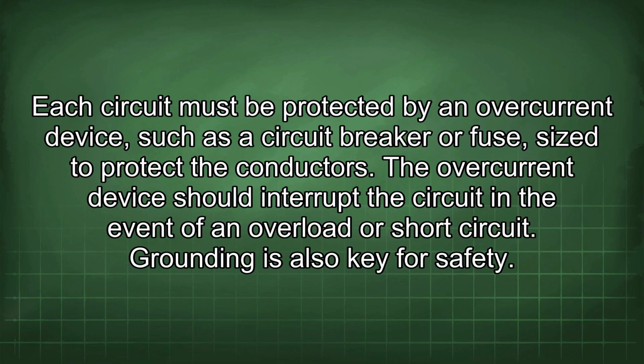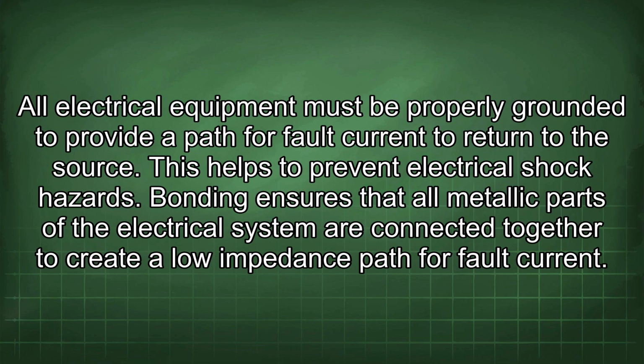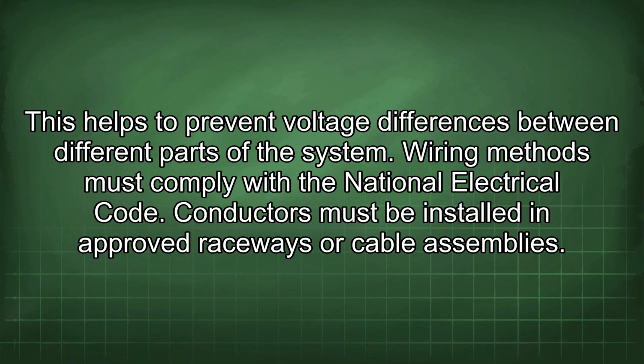Grounding is also key for safety. All electrical equipment must be properly grounded to provide a path for fault current to return to the source. This helps to prevent electrical shock hazards. Bonding ensures that all metallic parts of the electrical system are connected together to create a low impedance path for fault current. This helps to prevent voltage differences between different parts of the system.